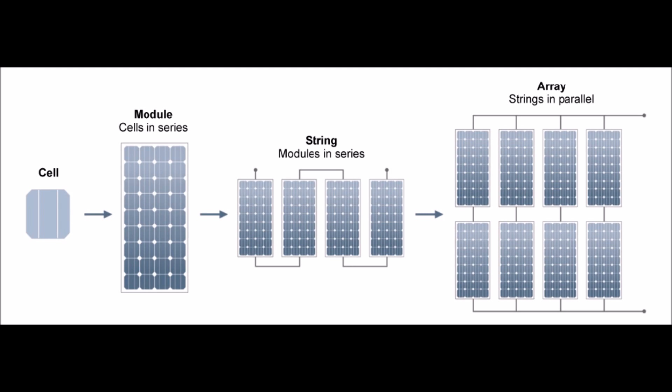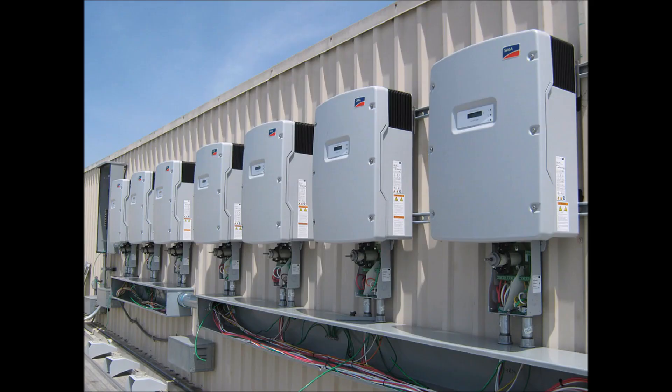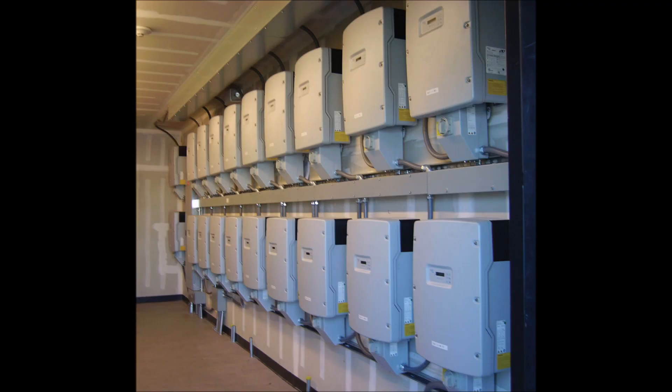First things first, let's talk about what we mean by a string. In solar we have several different units that we give names to. One of them is a string, which is solar panels that are wired in series — basically wired end-to-end in a long string. A string inverter takes all of the DC electricity generated by that string of solar panels and converts it into AC electricity. String inverters also operate at a much higher input voltage because when you wire solar panels in series you are increasing the voltage.